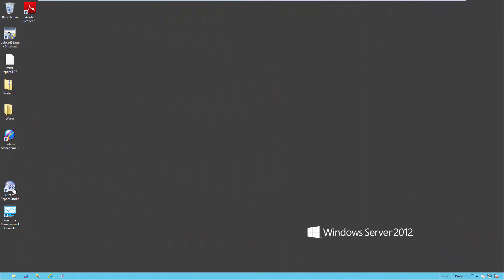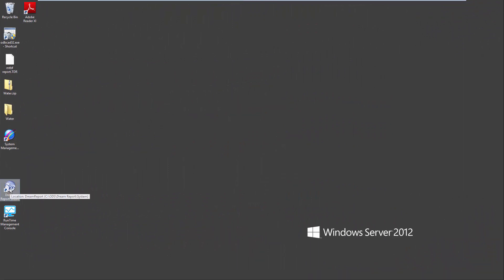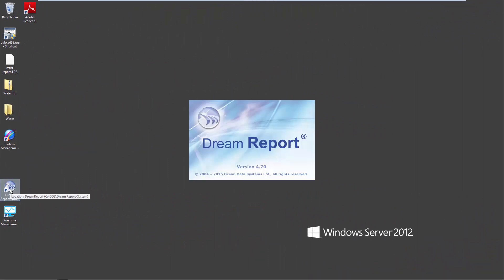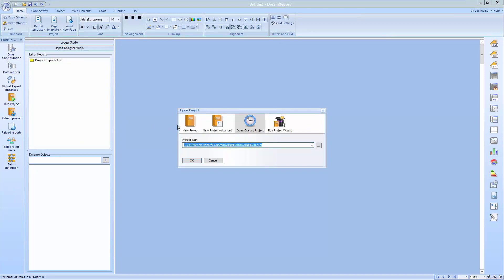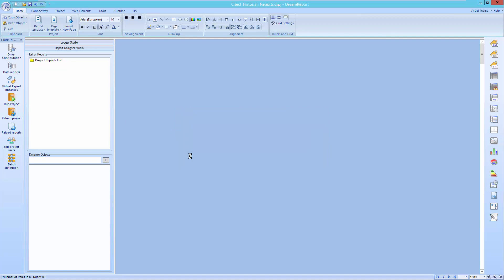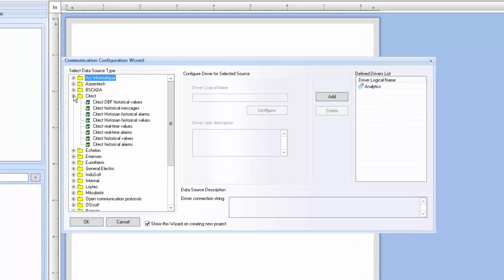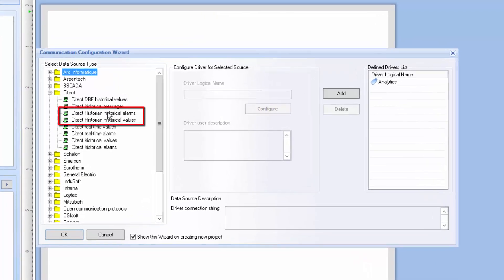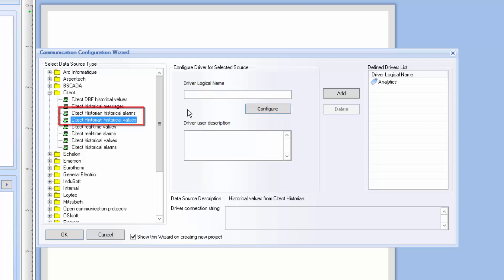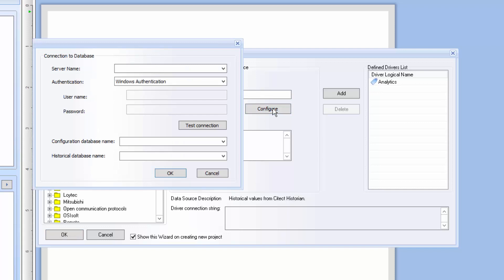I'm going to launch DreamReport Studio and create a new reporting project. I'll accept all defaults. After the blank project is created and Studio opens, I'll open the Communication Configuration Wizard and expand the list of Citect Communication Drivers. We'll only focus on the Citect Historian drivers in this demo. Configuration of the Citect SCADA drivers is covered in a separate video tutorial. In this first example, we go to the Citect section in our Communication Drivers window and configure an instance of the Citect Historian Historical Values driver. We first add a logical name and then configure the driver. We'll start by entering or browsing for the name of the SQL Server containing the Citect Historian configuration and historical databases. This SQL Server can be local to the DreamReport machine or on a remote machine.